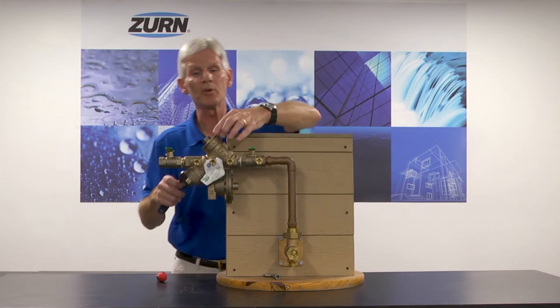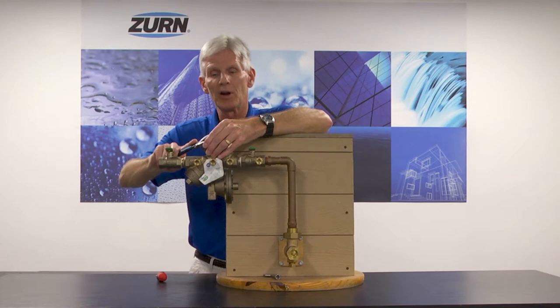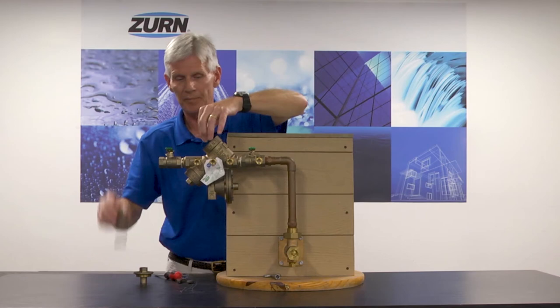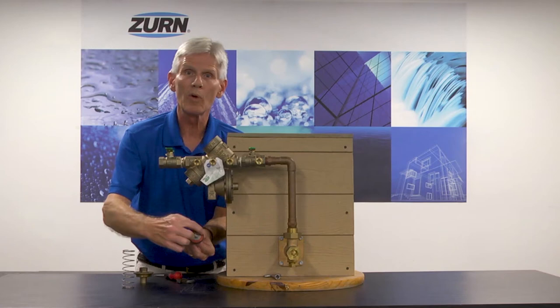Once we've got the test cocks open and the pressure has bled, the next step is to simply remove the number one poppet check cover, so this is the one pointing upward. Very straightforward, we loosen it up. We want to keep the palm of our hand over this cover because it is a spring-loaded cover. Once we get this cover off, inside we've got our spring and our black plastic poppet.